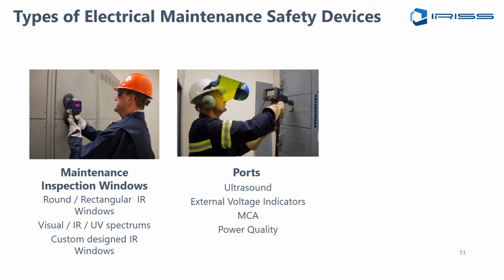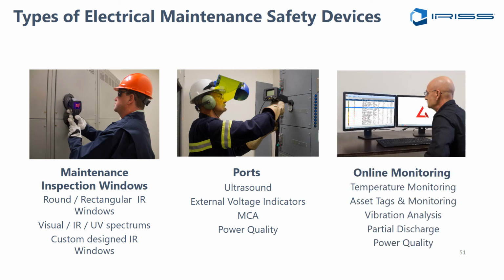The second is ports: ultrasound or partial discharge ports, external voltage indicators, motor current analysis tap-off points, power quality analysis tap-off points. All the time we're trying to bring these data collection points to the front, the safe side of the electrical panels that we're working on. And then finally, we're really advancing into online monitoring: temperature monitoring, asset tags, data management, vibration analysis, PD analysis, power quality analysis. This is really starting to grow with the industrial Internet of Things and its adoption within industry. People are starting to utilize the vast amounts of money their organizations have spent on online systems, and piggybacking the reliability data is a great way forward.